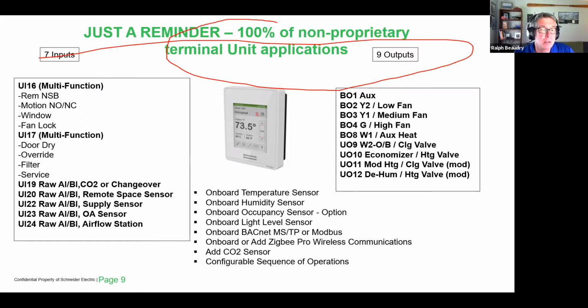If we don't use it for that, we can use it as a raw analog input. Then we have 5 additional AI/BIs, which we call universal inputs. They can be used for any kind of sensor you want to bring into the room controller, like a thermistor or a 0 to 10 volt input, and they're also used within our application if they're not used for the standard one. So if I want to use a CO2 sensor to drive an economizer, I'm going to use UI 19, and so on.